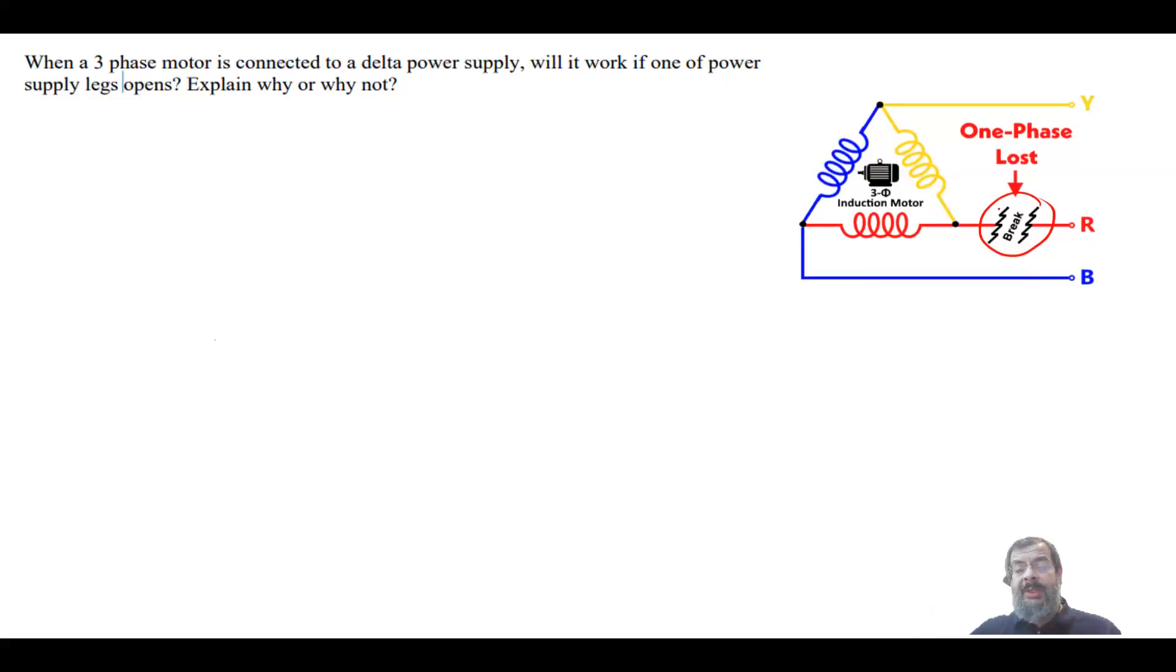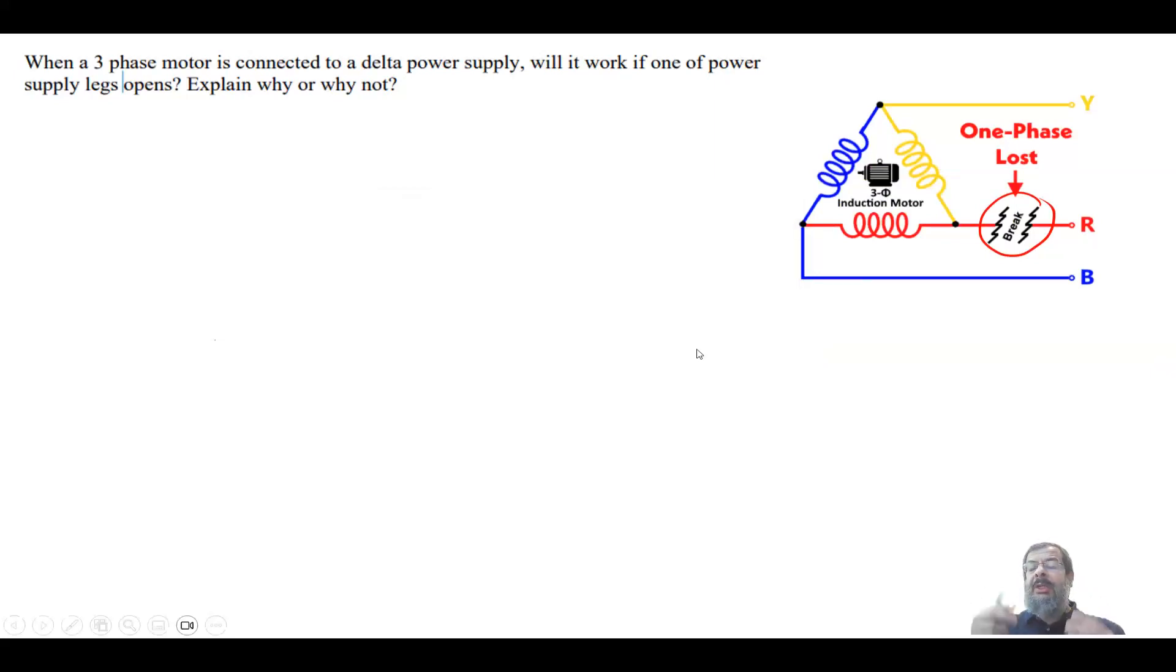Basically, what will happen is the motor, when one of the supplies is open circuit, will try to draw more current to compensate. And when you draw more current, you will have overheating of the motor. If the motor has thermal protection, it will disconnect.